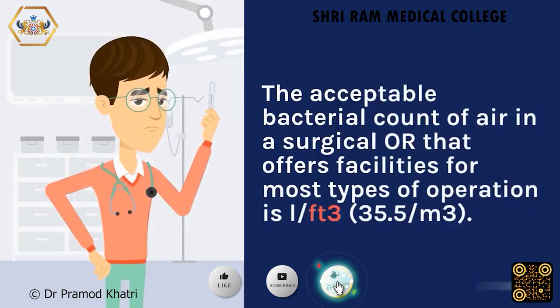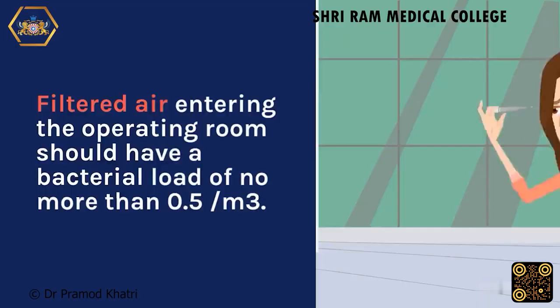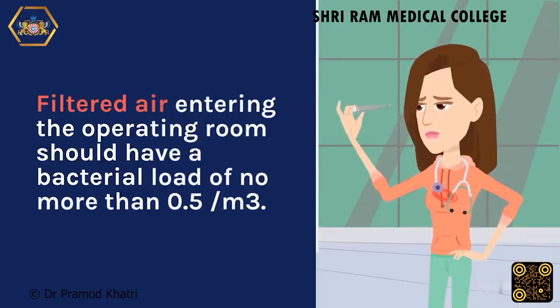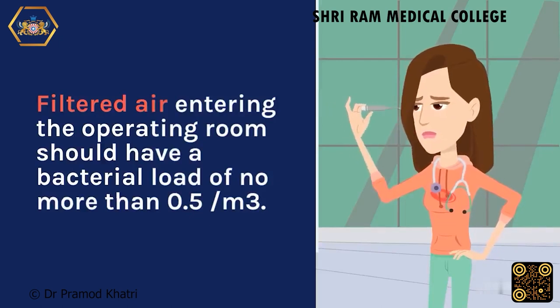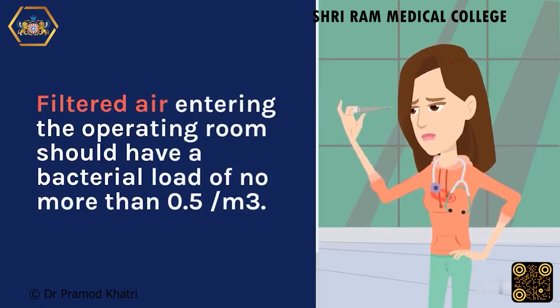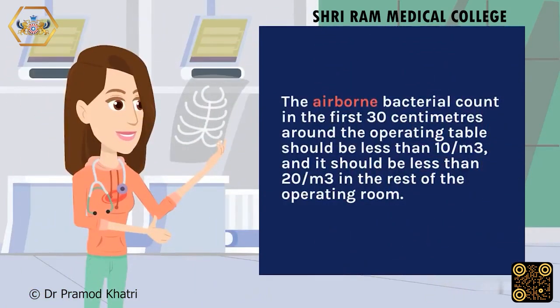The acceptable bacterial count of air in a surgical OR that offers facilities for most types of operation is 1/FT3, 35.5/M3. Filtered air entering the operating room should have a bacterial load of no more than 0.5/M3. The airborne bacterial count in the first 30 cm around the operating table should be less than 10/M3, and it should be less than 20/M3 in the rest of the operating room.